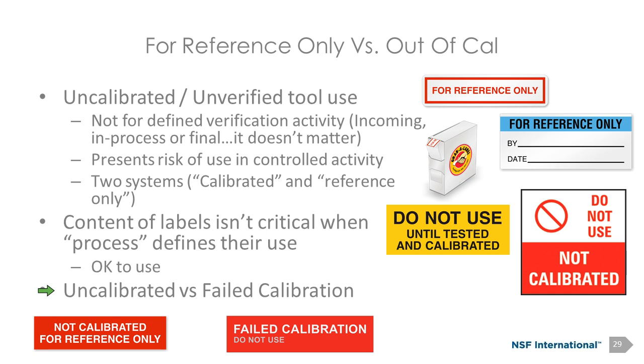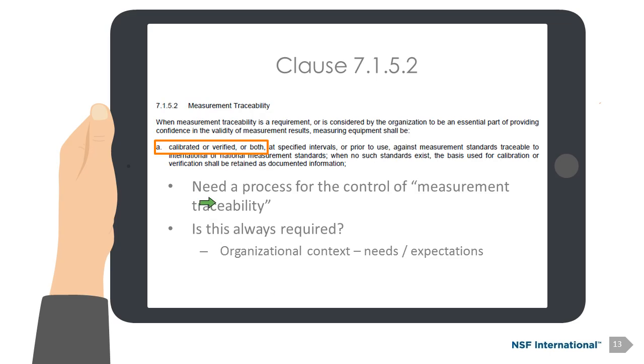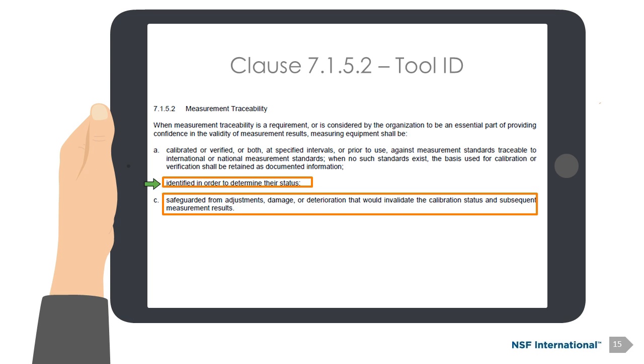The last bullet here talks about uncalibrated versus failed calibration. If I have a tool that comes back as bad, do I really want to put a for reference only kind of sticker on it? That's where we probably want something else to call it a non-conforming tool, whether it's a non-conformity report from our system, or a failed calibration, do not use, something that's way more clear of the status of that tool. Because again, going back to the requirement from 7.1.5, it says, identified in order to determine its status. So we probably need to be thinking about how we should be labeling it so that it doesn't create that ambiguity. Okay?